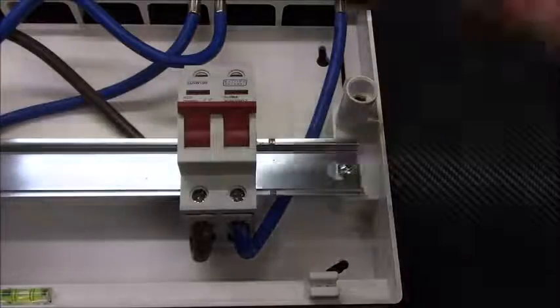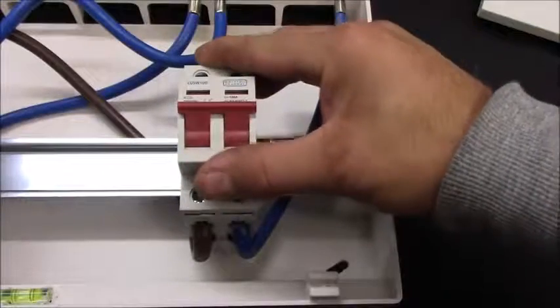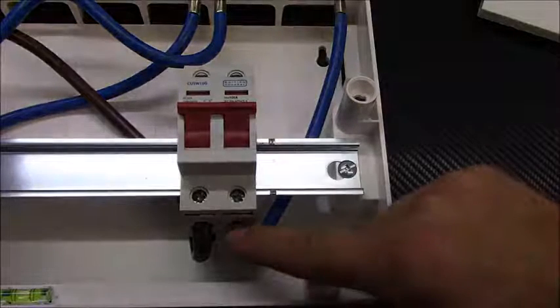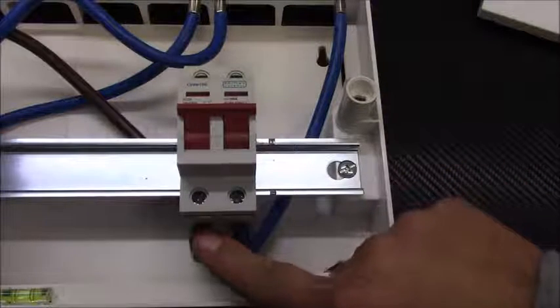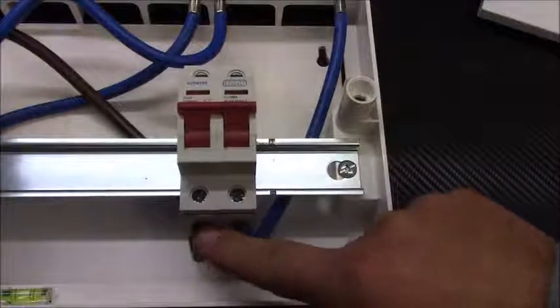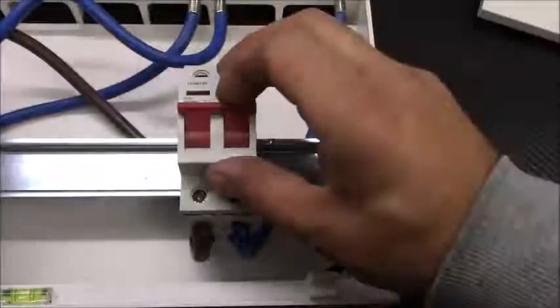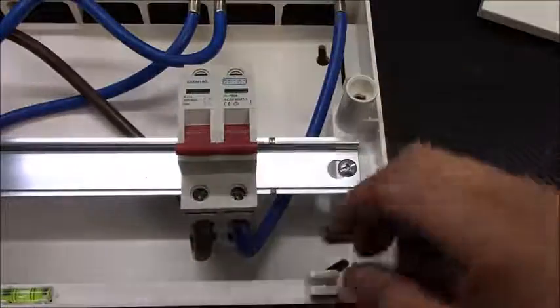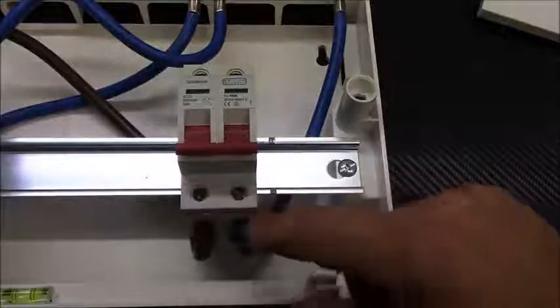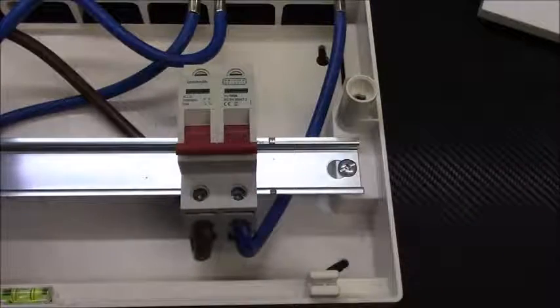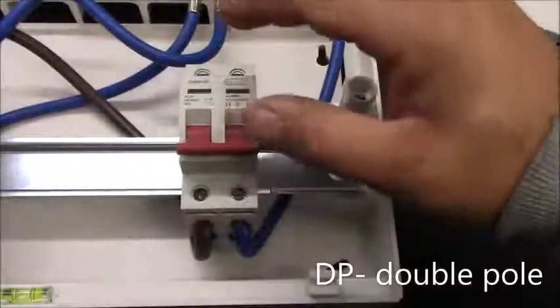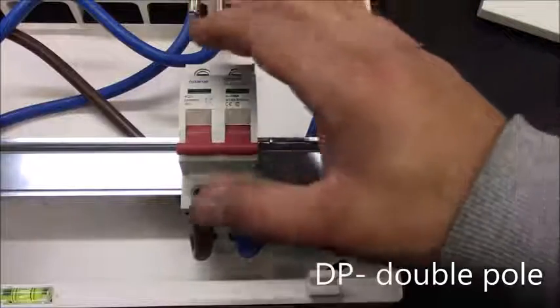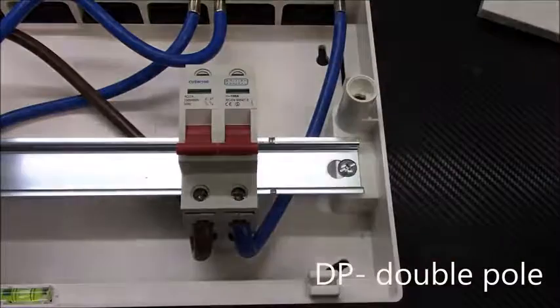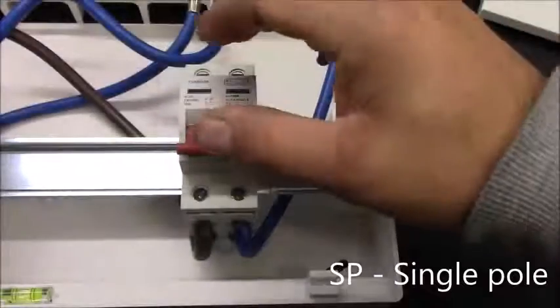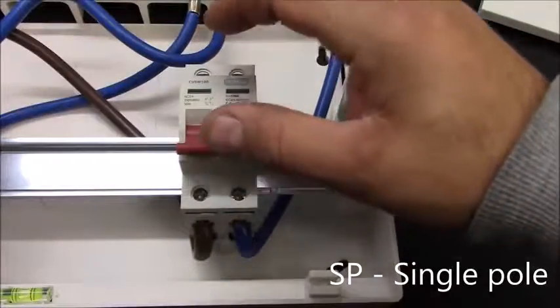A good example of a double pole switch is the main switch at the consumer unit. You see it's got neutral and live cables going into it. So when you switch it off, this disconnects both the live and the neutral. So DP or double pole means this disconnects both neutral and live, and SP or single pole means this disconnects only the live wire.